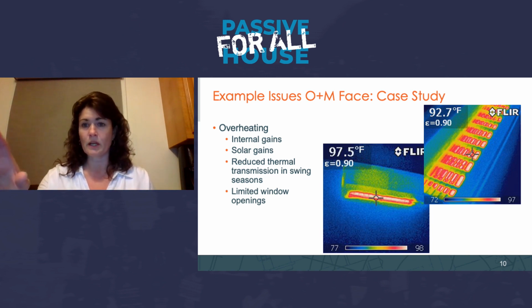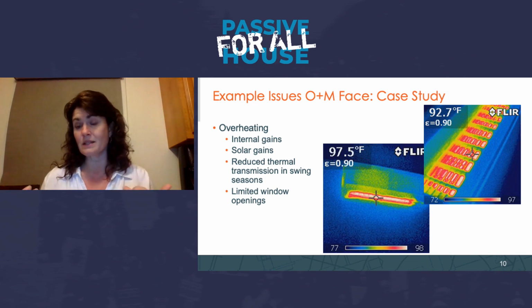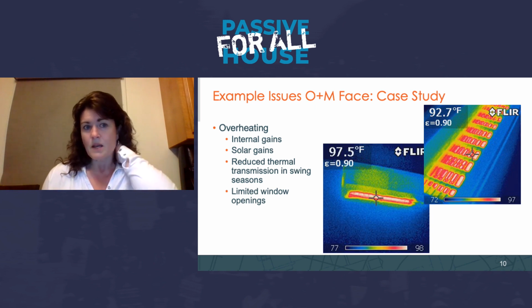and a floor-mounted unit on the right. You can see the heat that's coming out of those evaps, and that is just heat that's bleeding out. Neither of these units is actually calling for heat. It's warm in the apartment. I think you can see, it looks like the coldest surface in the right side picture is 72 degrees, and on the left is 77 degrees. So it's very warm in those rooms. So neither's calling for heat, but heat's coming out of those evaps anyway, because they're only in heating or cooling mode, right?